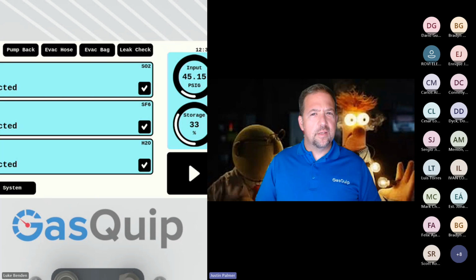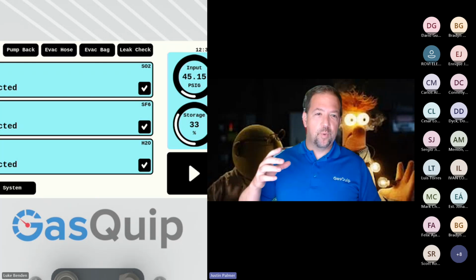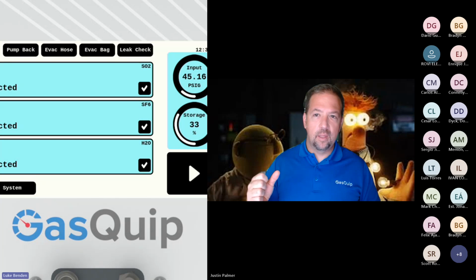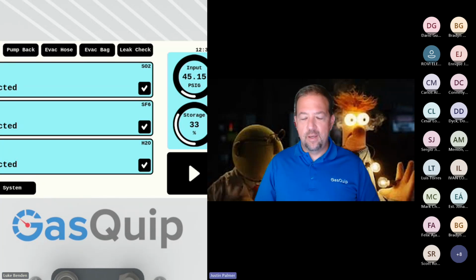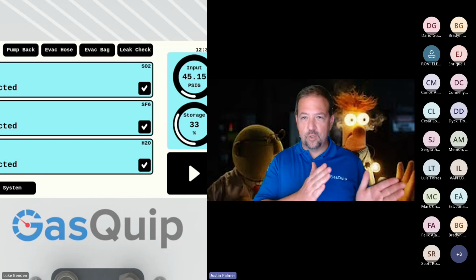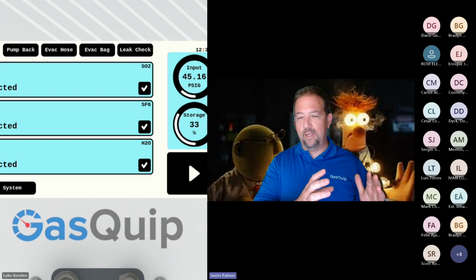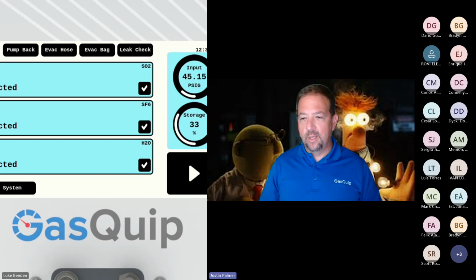And I'm asking so I can remember as well, when they go to do a recalibration, the cost is to get the device set up for it. The sensor itself is going to be the same one no matter what, right? That's correct. Okay, so Doug, that's just an initial deal on the device because it's done mathematically versus having a special sensor for it, and that's the way I know you guys have used the Dilo units. There's a direct correlation between what volume percent you're reading and what it actually is if it's CF4. So it works off that same principle.